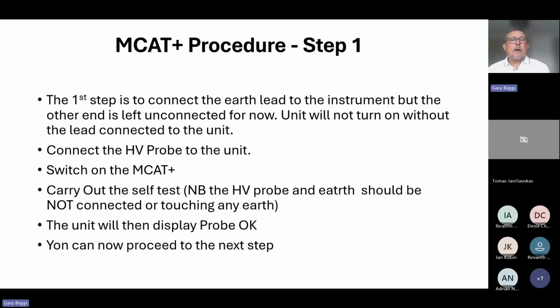Now the unit will carry out a self test. So what the unit does is it checks all its wiring, all its connections, and makes sure that it's happy with everything. So the HV probe and the earth lead should not be connected or touching any earthed point or anything. It needs to be floating. Once you carry out that test, in theory, the unit will then display probe OK, and that's telling you that it's done a test, looked at its internal wiring, checked all its connections and checked itself, as it were, and found it to be OK. Then you can proceed to the next step.